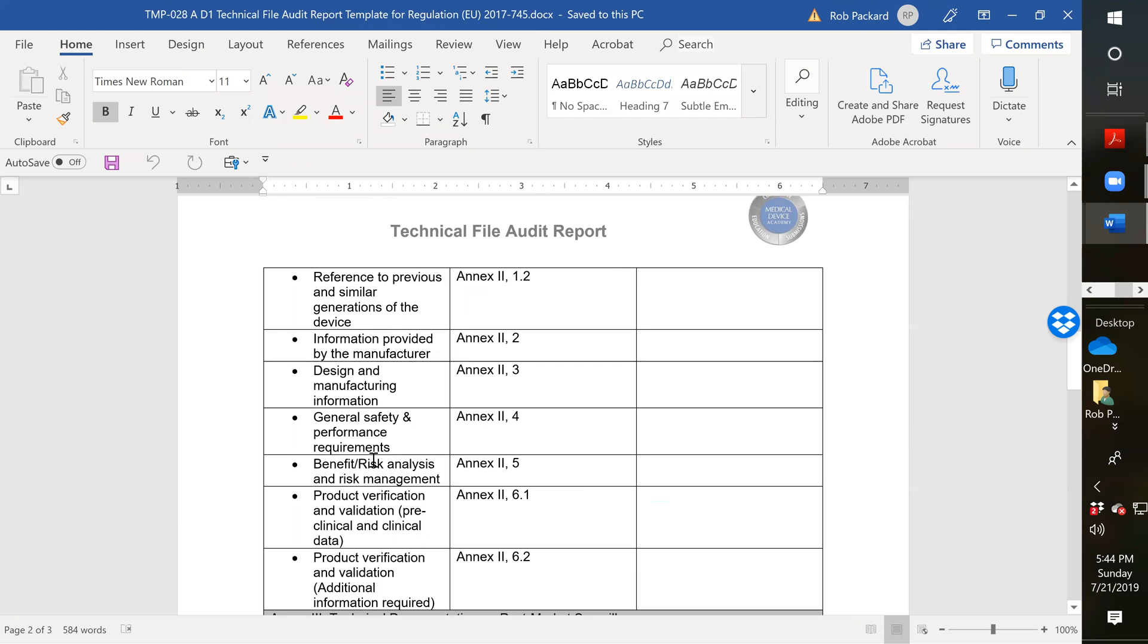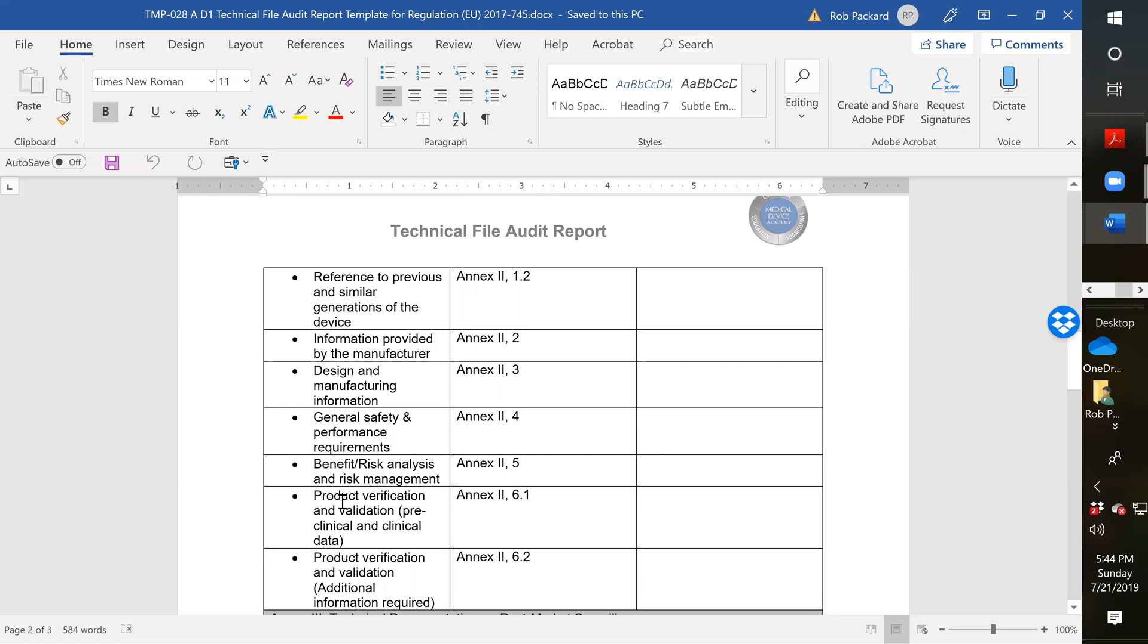Benefit risk analysis, they should still be doing a benefit risk analysis. But one of the things you want to keep in mind here is that the risk analysis requirements are now Annex 1 sections 1 through 9, which is different from what was in the MDD in sections 1 through 6. And then in addition, the ISO 14971 standard is going to be updated later this year. So in fall of 2019, we're going to have a new risk management standard that we need to address as well. There are definitely some subtle changes that are going to make a difference. So companies are going to have to look at the risk management file and their benefit risk analysis and update those as well.